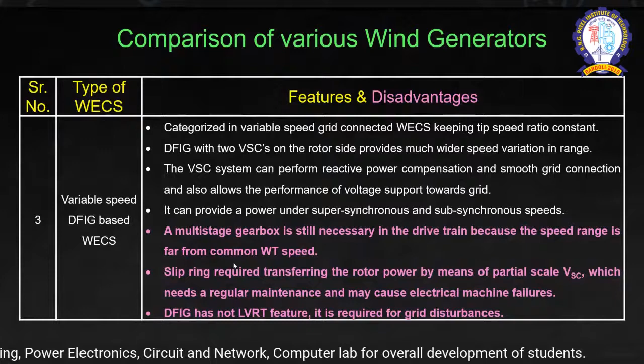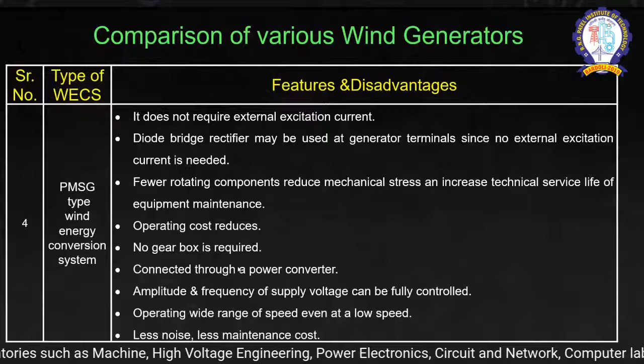Talking about the main feature of the permanent magnet synchronous machine direct drive system: as our rotor is a permanent magnet, it doesn't require any external excitation from the grid or from a DC supply. In the ultimate case, we have various aspects of diode bridge rectifiers that may be used at the generator terminals. There are fewer rotating components, no gearbox, so the cost has been reduced. The amplitude and frequency of the supply voltage can be controlled, and it creates less noise and pollution.